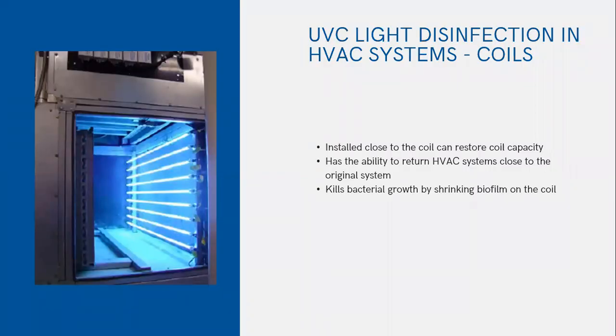UVC light disinfection in HVAC systems on the coils — let's talk about this. These systems are installed close to the coil, as you can see in this photograph. They can help restore coil capacity, whether you're installing them in a brand new building as part of new construction or in an existing building. They have the ability to return HVAC systems close to their original performance, and they kill bacterial growth by shrinking biofilm on the coil. You can go back into our YouTube library and check out our messages on biofilm in HVAC systems.